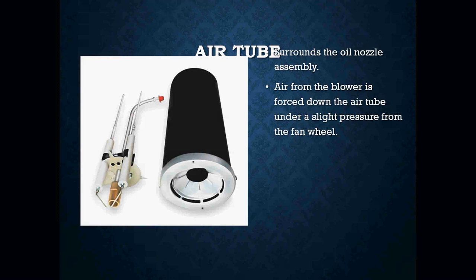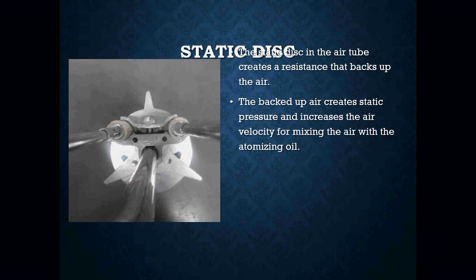Your air tube surrounds the oil nozzle assembly. The air from the blower is forced down the air tube under a slight pressure from your fan wheel. Your static disc is in the air tube and creates a resistance that backs up the air. The backed-up air creates static pressure and increases the air velocity for mixing the air with the atomized oil.